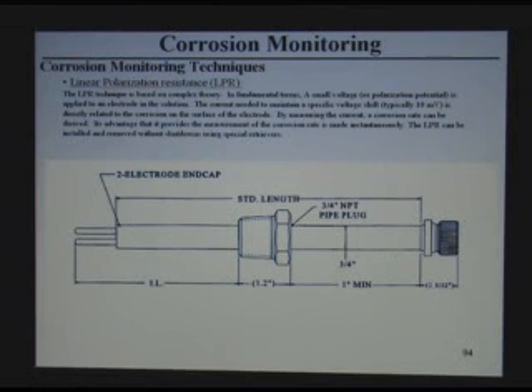Even these probes can be connected to the control room to give you a reading, and can affect things like ammonia injection. It can be used to control a lot of things automatically, as part of the control system. But this is only applicable when you have a water stream electrolyte system. It doesn't work with hydrocarbon liquids or similar, because they're not really electrolytes.